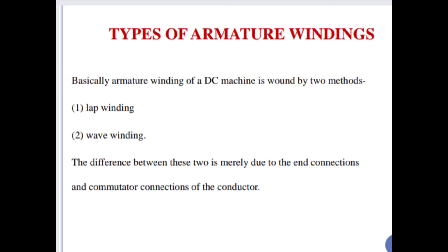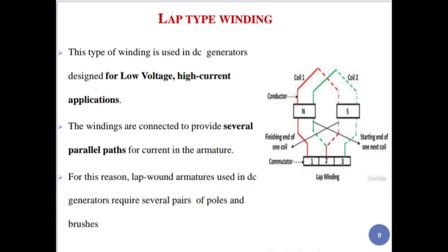Now, the types of armature winding. Basically, the armature winding of a DC machine is wound by two methods: first is lap winding and second is wave winding. The difference between these two is merely due to the end connections and commutator connections of the conductors. Lap winding is used in DC generators designed for low voltage, high current applications.